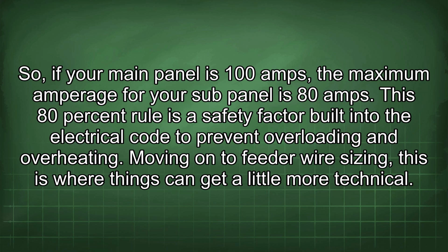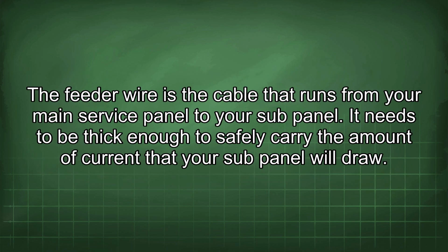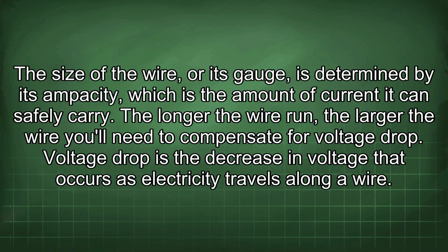Moving on to feeder wire sizing, this is where things can get a little more technical. The feeder wire is the cable that runs from your main service panel to your sub-panel. It needs to be thick enough to safely carry the amount of current that your sub-panel will draw. The size of the wire, or its gauge, is determined by its ampacity, which is the amount of current it can safely carry. The longer the wire run, the larger the wire you'll need to compensate for voltage drop.